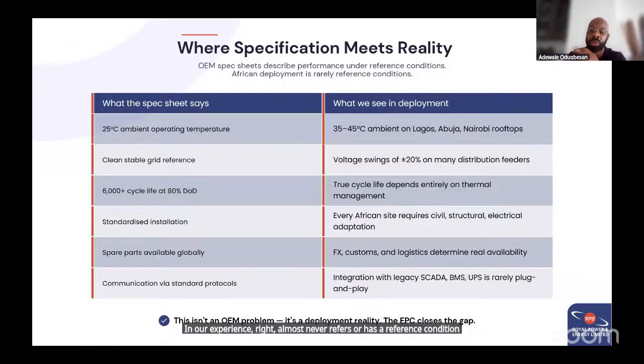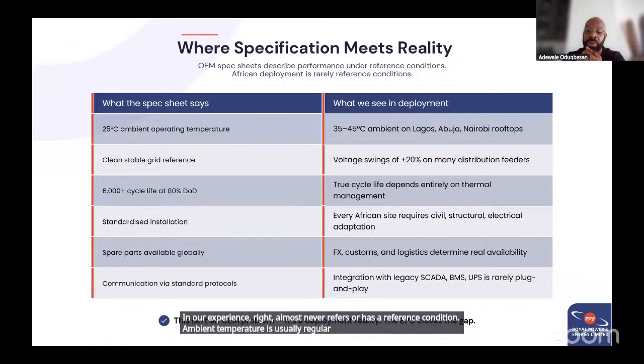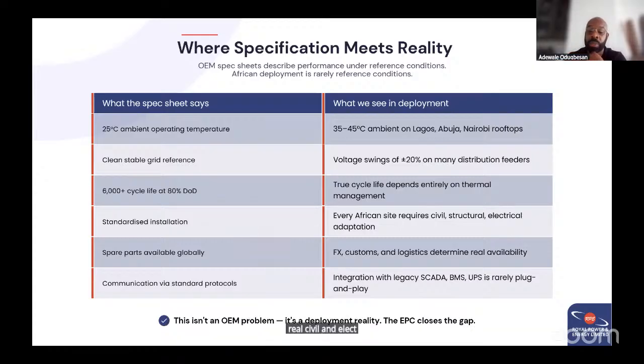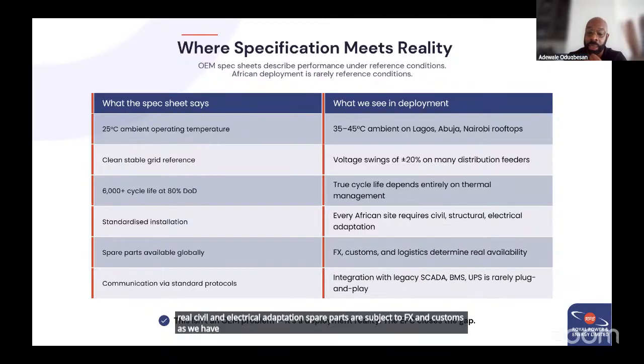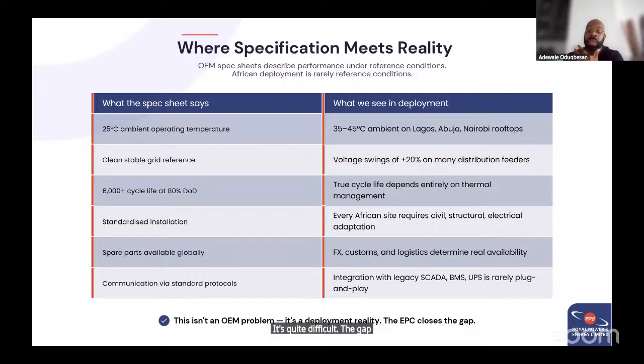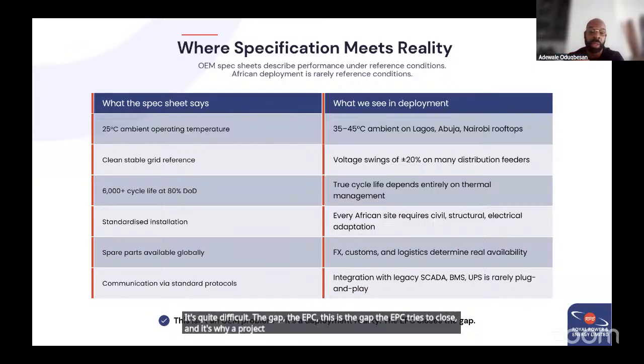Ambient temperatures usually run 10 to 20 degrees above spec. Grids are very dirty, and every site needs some real civil and electrical adaptation. Spare parts are subject to FX and customs, as we have in Nigeria, and integration with whatever legacy infrastructure the client already has—a UPS, BMS, SCADA systems—is quite difficult. This is the gap the EPC tries to close, and it's why a project looks straightforward on paper and often isn't during deployment.